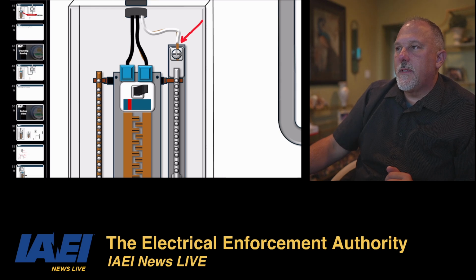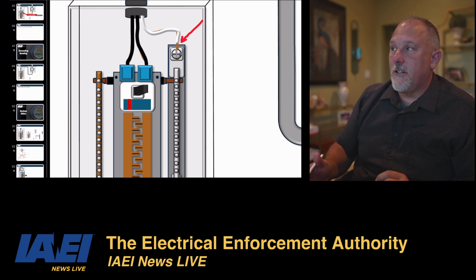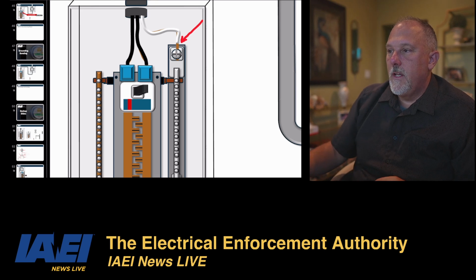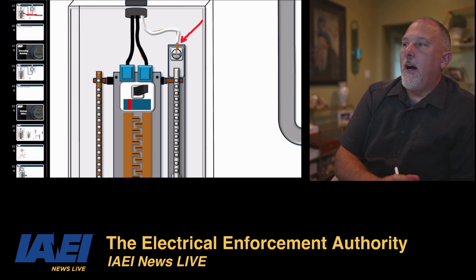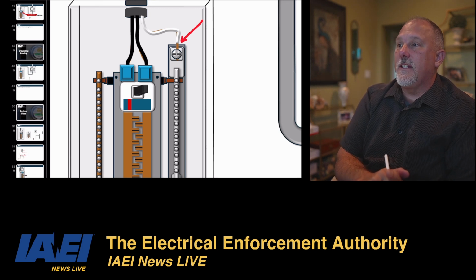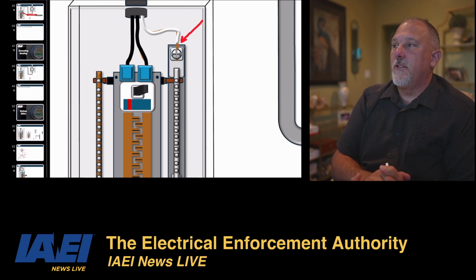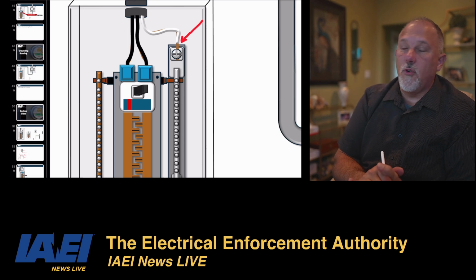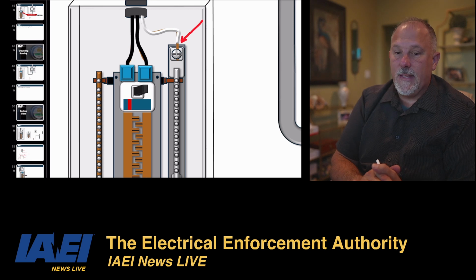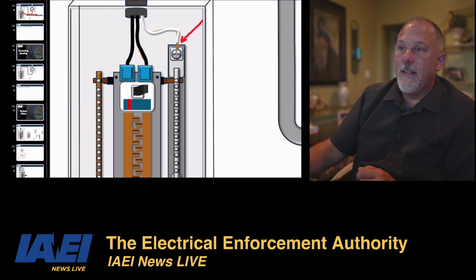The main bonding jumper for grounded systems: an unspliced main bonding jumper shall be used to connect the equipment grounding conductors and the service disconnect enclosure to the grounded conductor within the enclosure for each service disconnect. So in accordance with 250.28, we already talked about 250.28. If an AC system operating at 1,000 volts or less is grounded at any point, the grounded conductors shall be routed with the ungrounded conductors to each service disconnecting means and shall be connected to each service disconnecting means grounded conductor's terminal or bus. All right, that's what we're talking about right there. That is D. That is 250.24D.